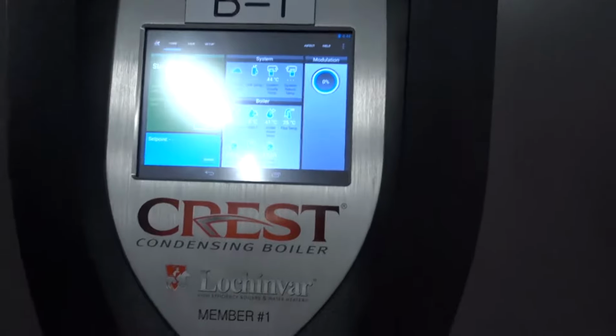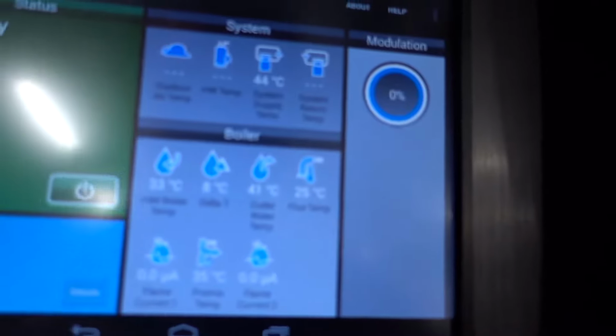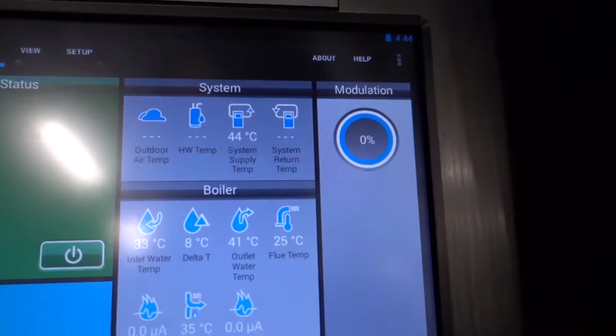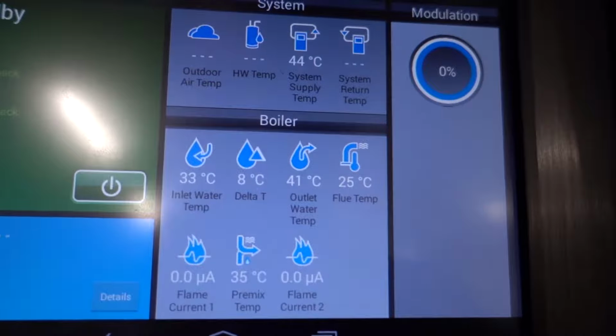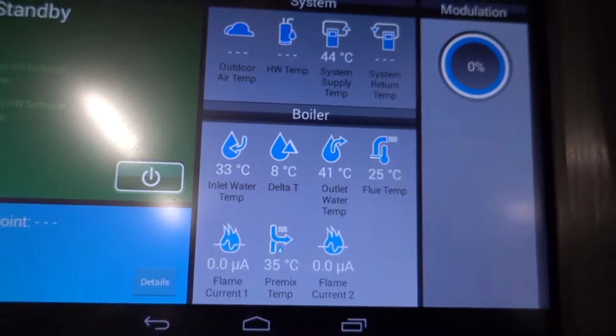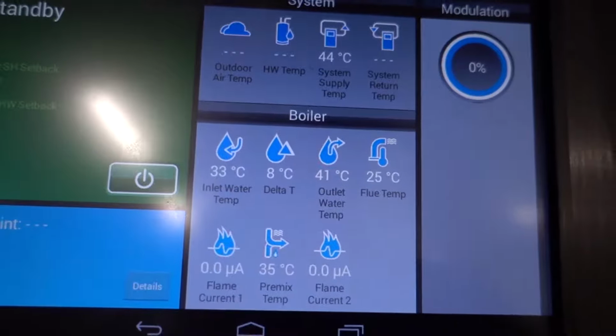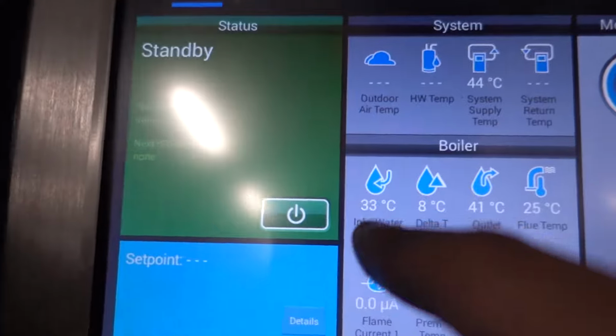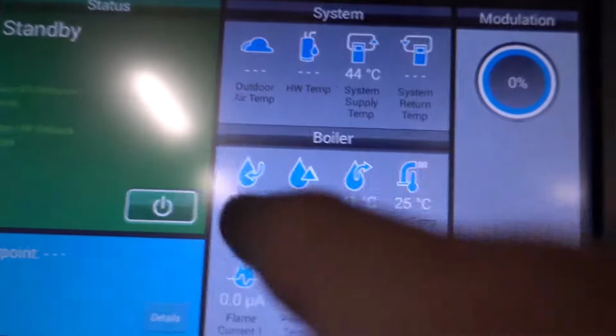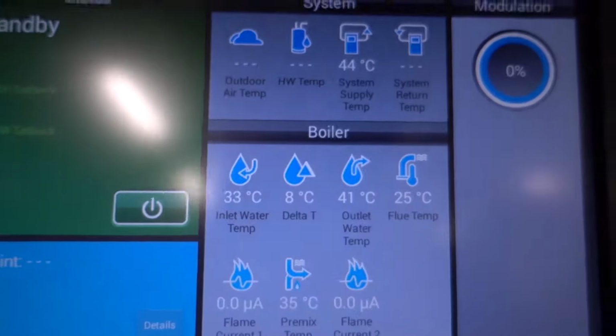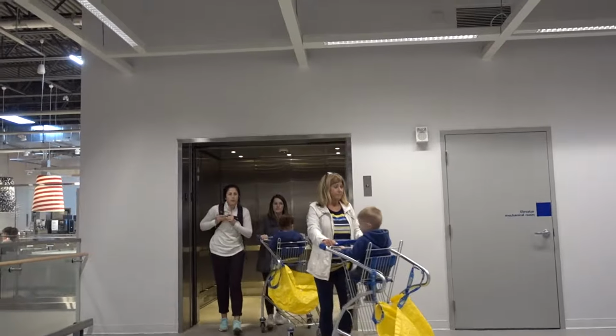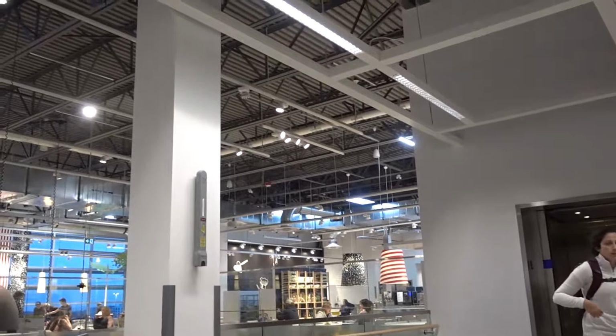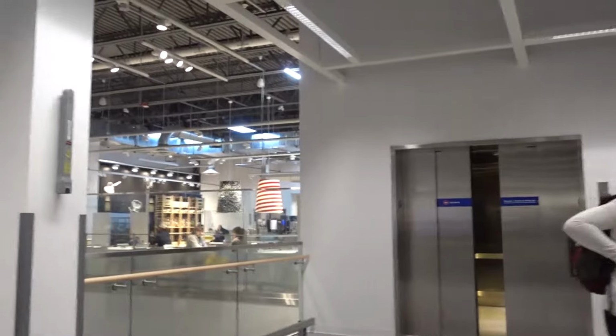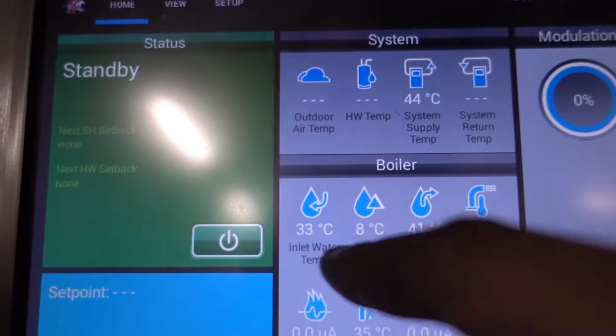Behind me are the boilers. So one of the things when we design this is, do we have enough capacity to fully satisfy the heat load? We went with the 60%. So 60% of the total heating capacity comes from the heat pumps. The remaining 40% gets made up from the boilers. Now, the reality is that boilers shouldn't come on very often. We actually generate more heat and trap that heat in the building more effectively than perhaps the energy model showed. So in reality, these are more backups.